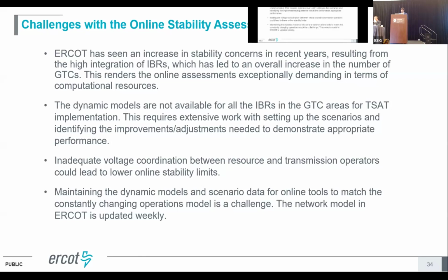It has to do that for several different contingencies, assessing all of them at each transfer level. Right now, with only 6 GTCs enabled in our test system, it's already taking about 5 to 6 minutes. If we run the full 24 GTCs, it will take at least 20 to 25 minutes, so we won't be able to run it as frequently. We run it every 10 minutes now, but we may have to extend that.